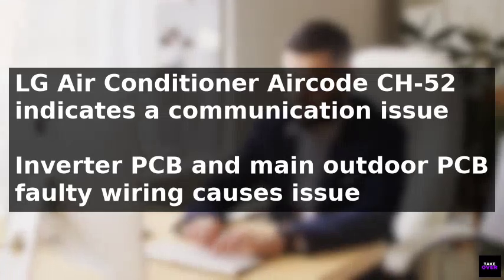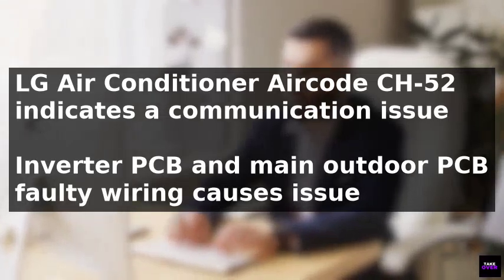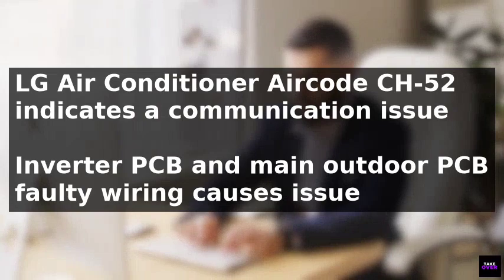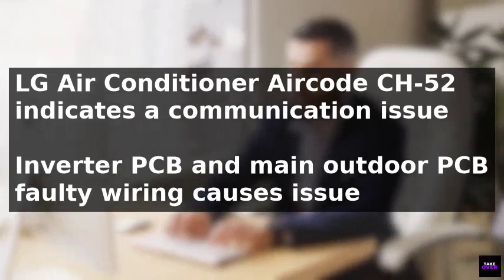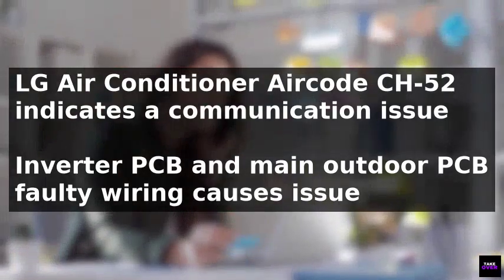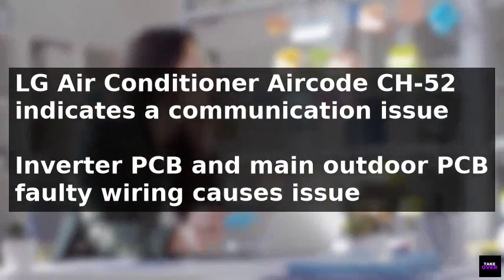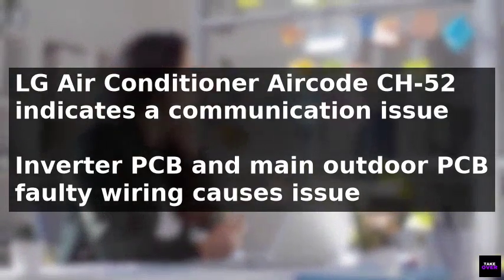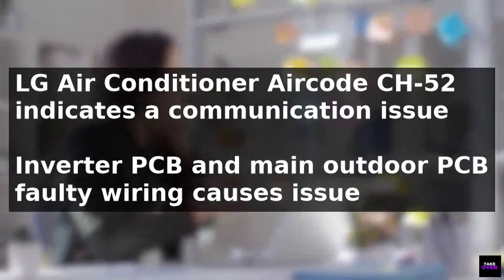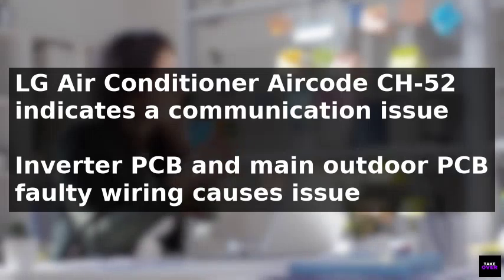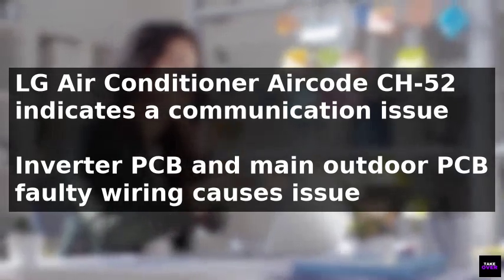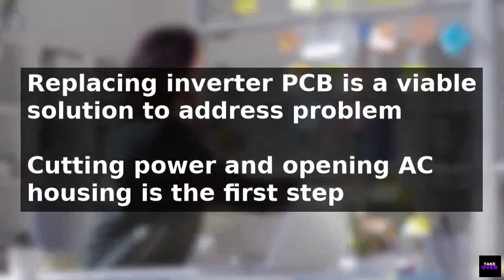The LG air conditioner aircode CH52 indicates a communication issue between the inverter PCB and the main outdoor PCB, often caused by faulty wiring or a malfunctioning inverter PCB. To address this problem, replacing the inverter PCB is a viable solution.